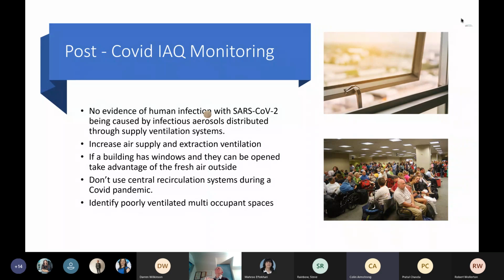from the ventilation systems. You can close the recirculation valve on the system, preventing it being recirculated, but you need to be aware that they have a leak percentage, and this leak percentage is recognised at installation stage. You can have up to 3% leak percentage. So even though you shut that valve, it will still have a bit coming out.